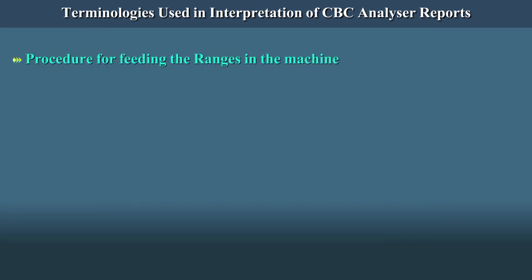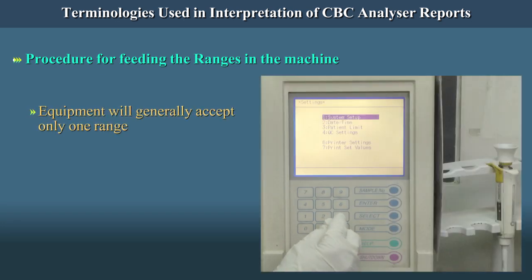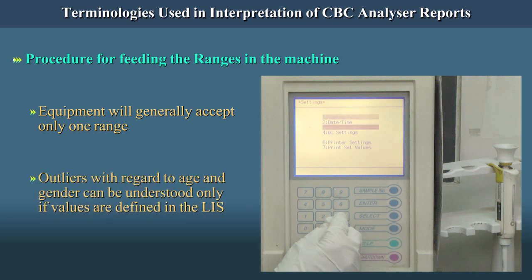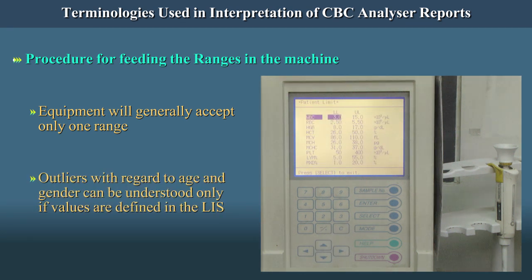Procedure for Feeding the Ranges in the Machine. The equipment will generally accept only one range. So outliers with regard to age and gender can be understood only if the values are defined in the LIS.